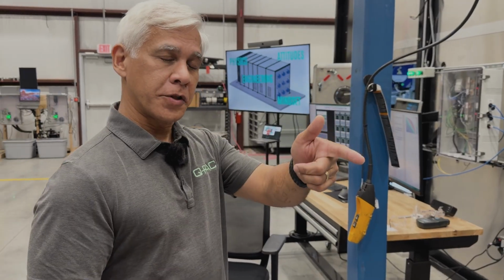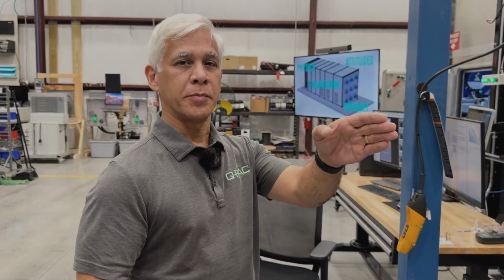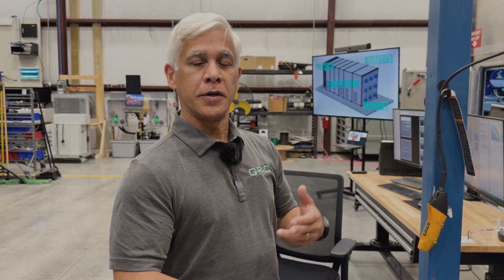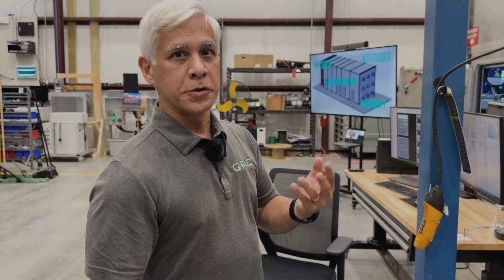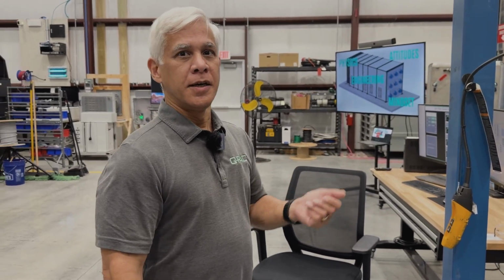So we can measure the static pressure across the fan wall. So we have airflow and we have pressure. Those two numbers will let us build the fan curve, which tells us the performance of that fan. The third thing we measure, which I did mention, is the power. By measuring the power, the airflow, and the static pressure, we can generate the power curve and calculate the efficiencies. So all of this tunnel was built to calculate those three things accurately.